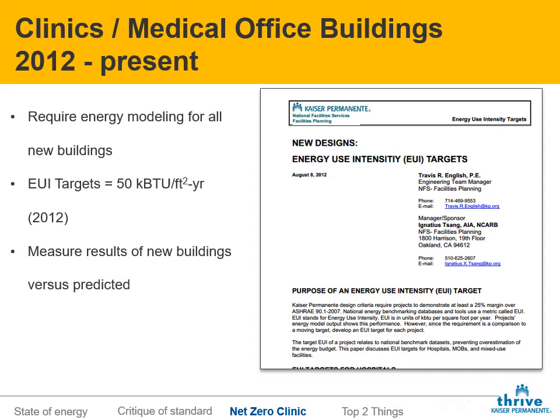So when we put this program in place, we kind of officially unadopted standard 170. Wherever it's not legally mandated, we don't use the air change rates, right? And then the third component of our energy program was that we measured the results. So we would always do an energy model during design, and we would measure results after design.